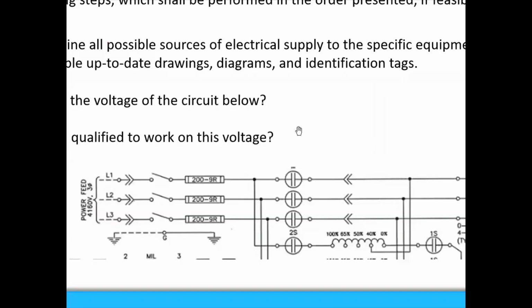And we can see that if this was equipment in our facility, it pretty much has one source of supply. It is 4160, so 4,160 volts, but the diagram gives us a great indication that we have that one source of supply. This happens to be a motor starter inside of a motor control center. So we have a disconnect with some fuses. We have some contacts in our motor starter. We have the ability to rack this in or out. And this is a reduced voltage motor starter. They're using an auto transformer to do this. But we can see here on this one, only one source of supply, which is really nice when that happens.